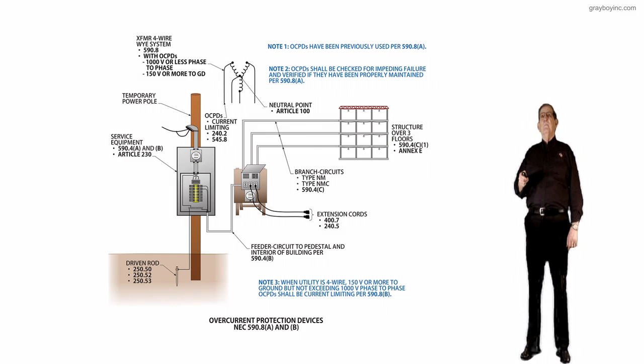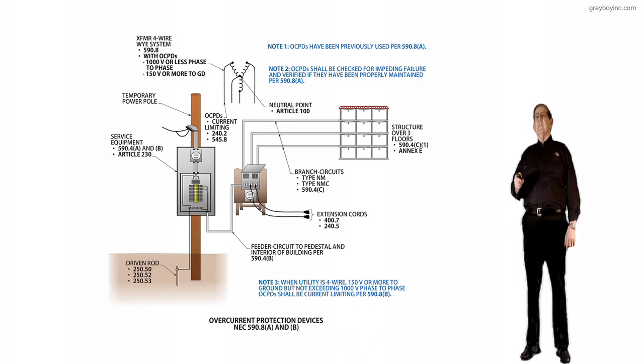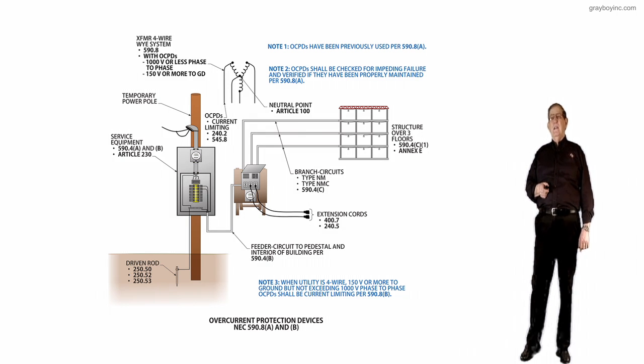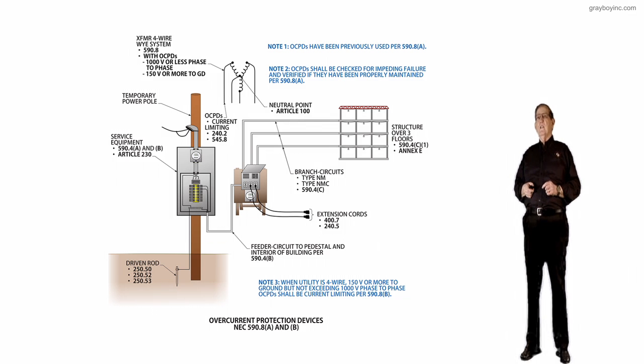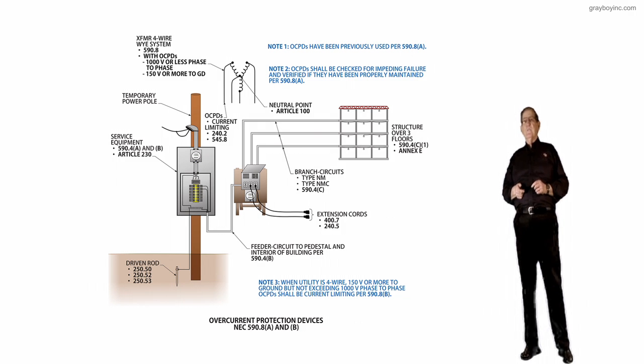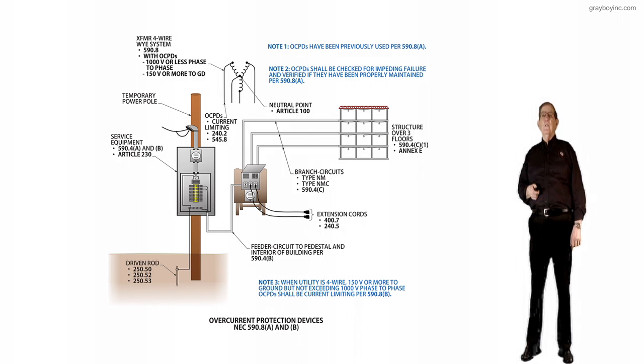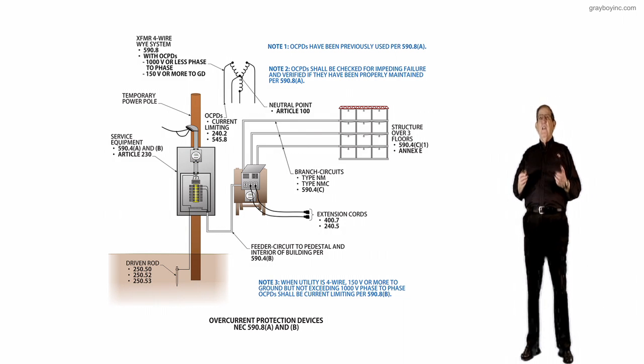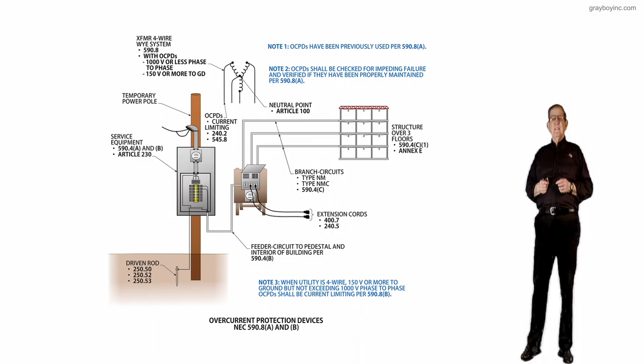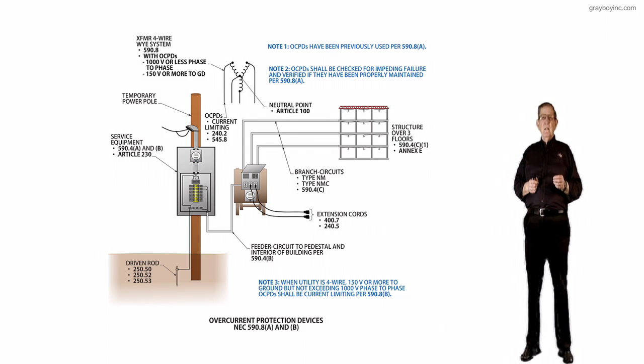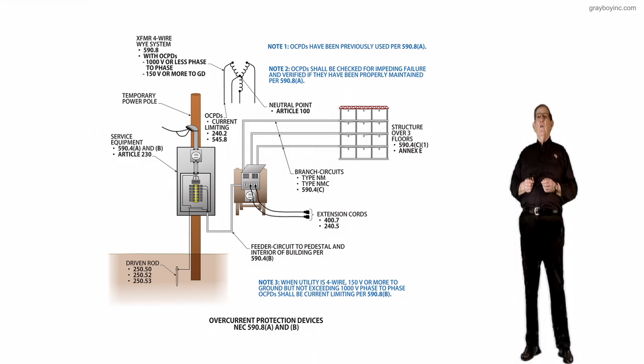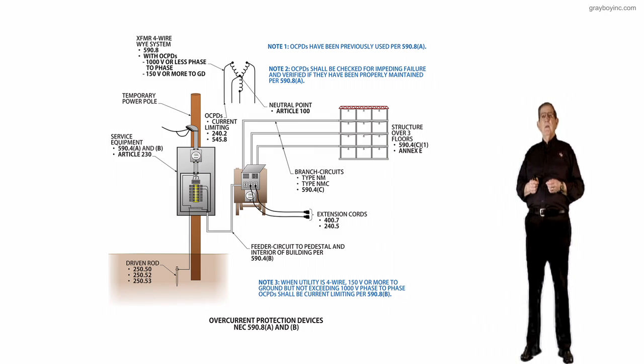Now let's review note 1. Overcurrent protection devices have been previously used per 590.8(A). We pick up our rules there. And you know, if you're dealing with reused and current limiting overcurrent devices, that you deal with 277/480 volt systems, see 590.8 for such rules. Now, note 2 states the overcurrent devices shall be checked for impeding failure and verified if they have been properly maintained per 590.8(A). Now, 70E and 200.1 with the informational note material there, it refers you over to NFPA 70B to maintain systems.